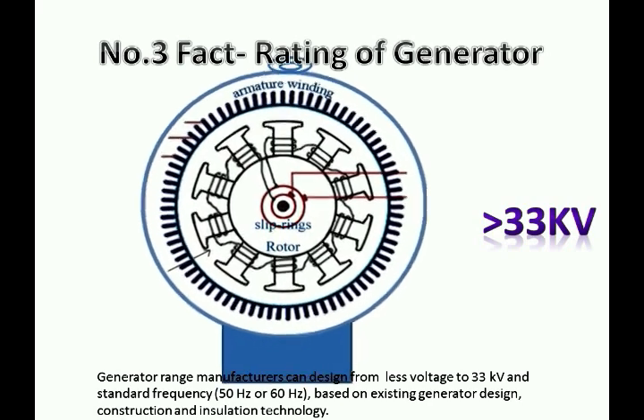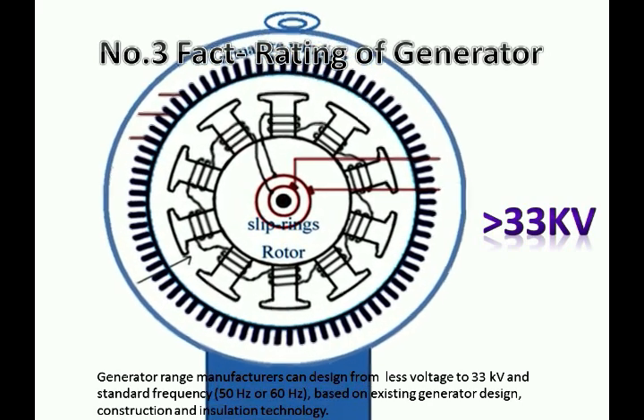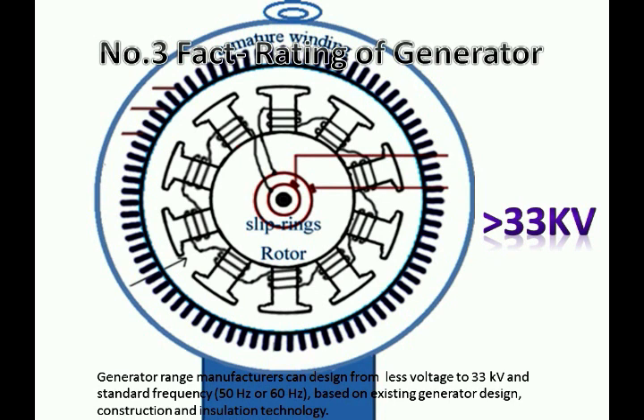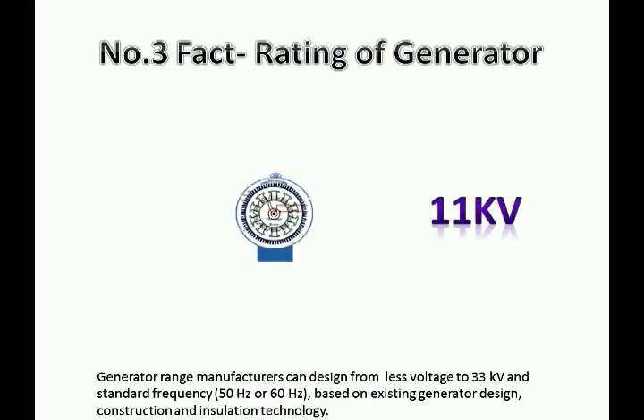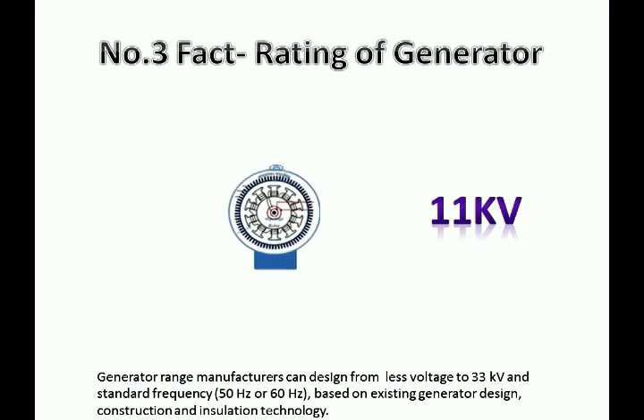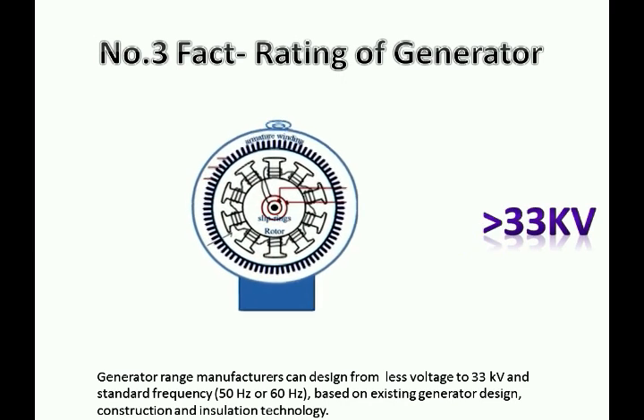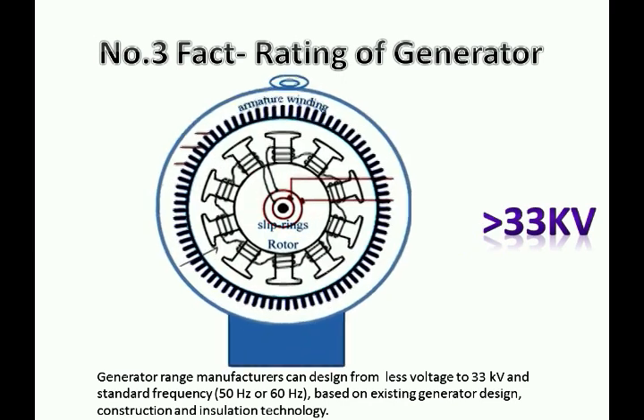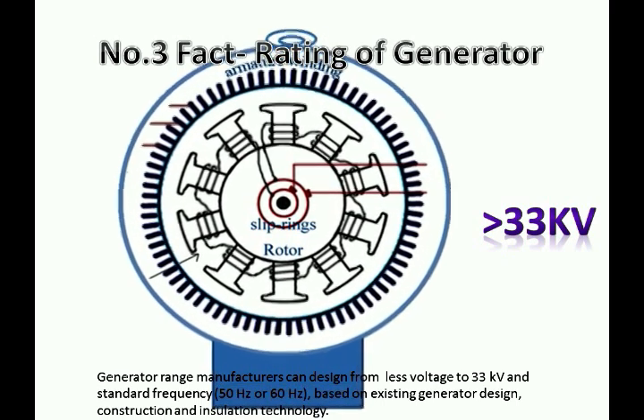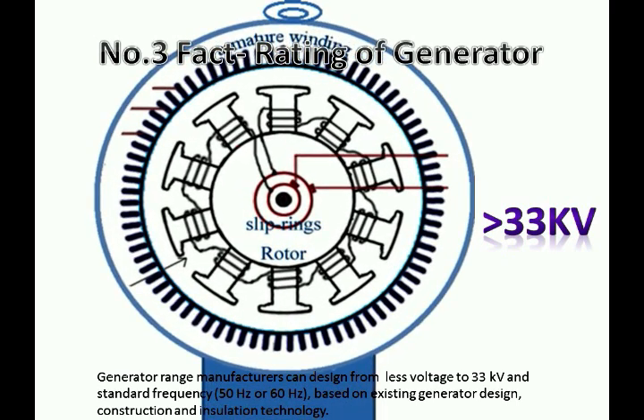But the insulation for the voltage level will be increased, so the generator size will be increased — twice the size of the 11 kV generator — and the turbine size will also increase relatively. Due to this, the cost is very very high. Also, if we want above 33 kV generator, then insulation will be the biggest problem and the size will also be very big. There will be technical difficulty in designing the alternator for a particular voltage and current rating. Hence, there is a need to balance between voltage and current, which is why we go for lower kV generators.